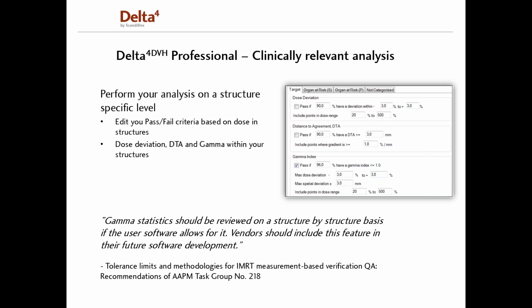From the publication Tolerance Limits and Methodologies for IMRT Measurement-Based Verification QA, recommendations of the AAPM task group number 218: gamma statistics should be reviewed on a structure-by-structure basis if the user software allows for it. Vendors should include this feature in their future software development. With the Delta4 DVH Professional software option, you will obtain your gamma pass rate, dose deviation, and distance to agreement inside each structure.